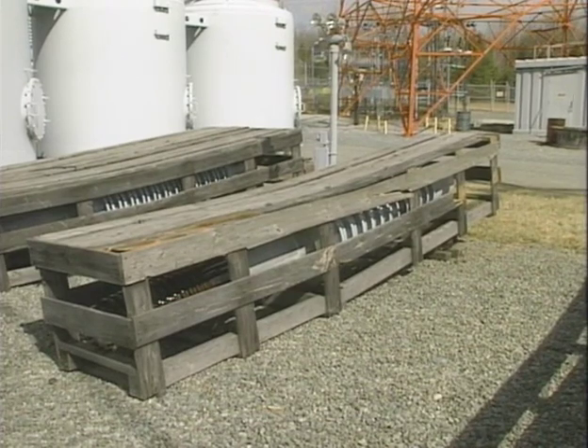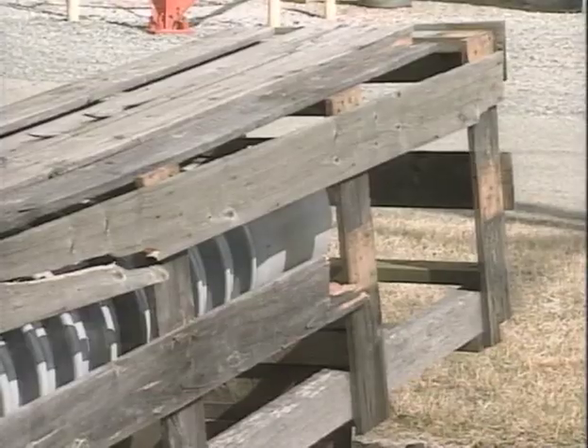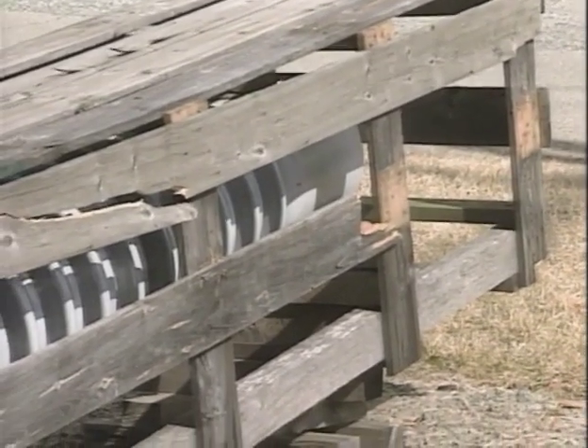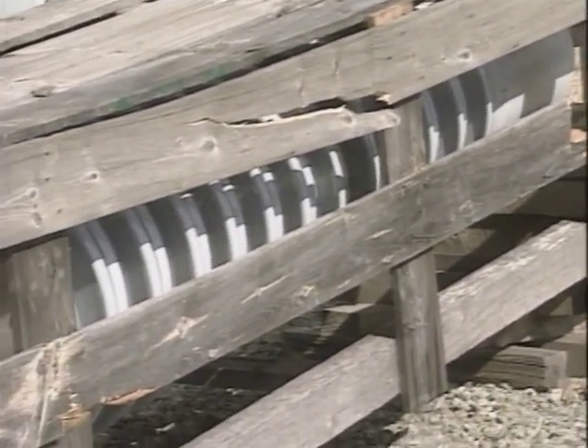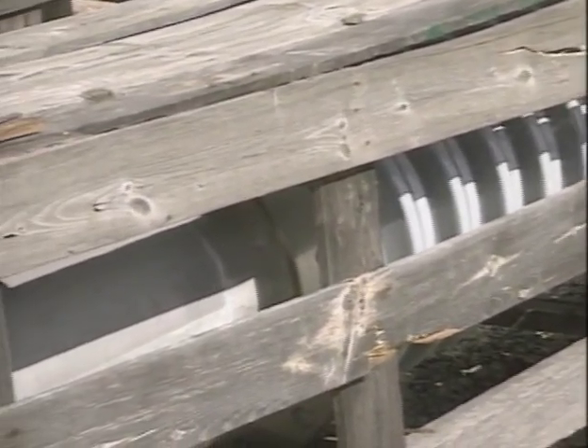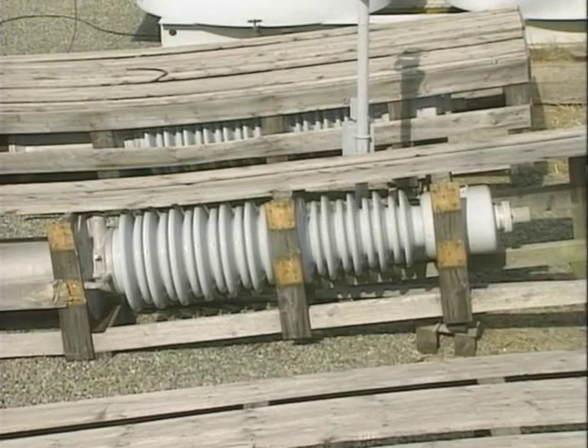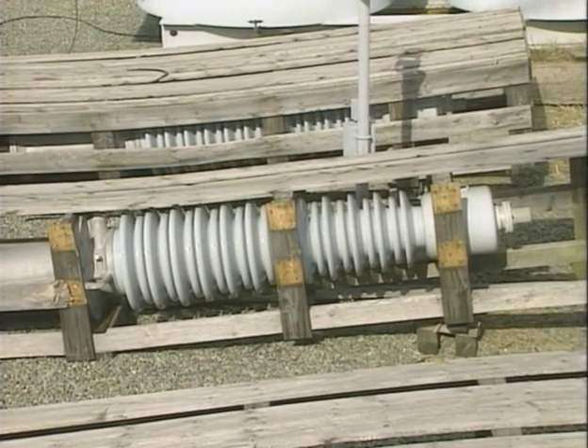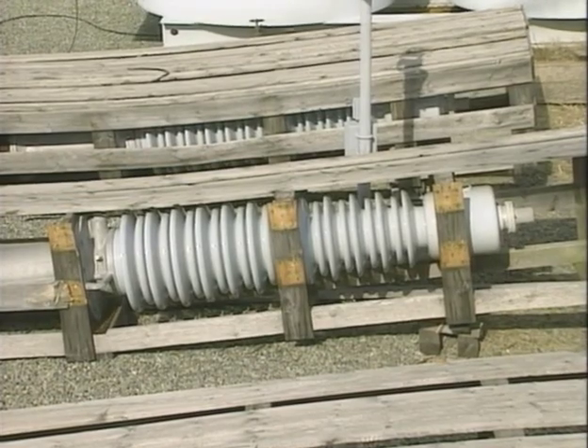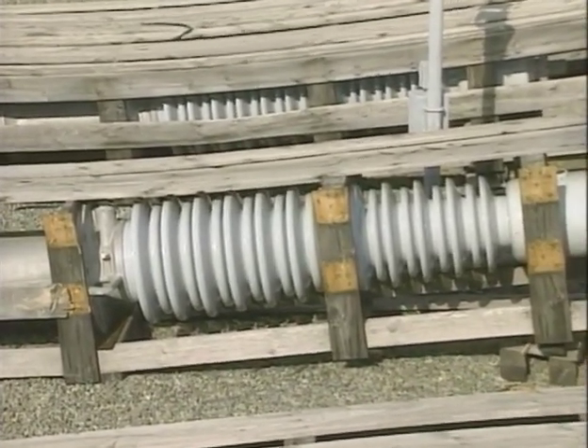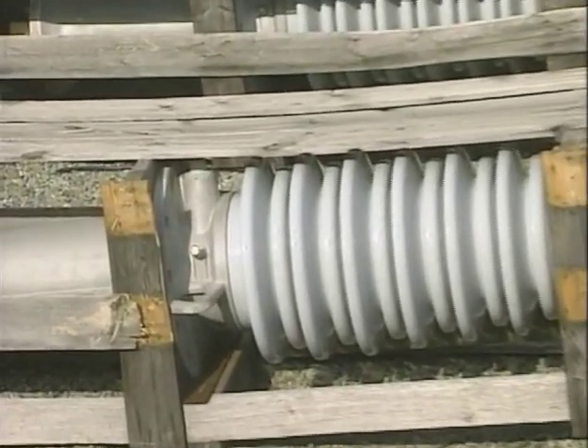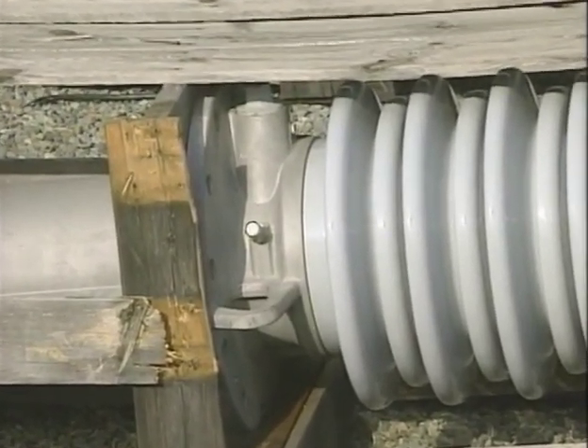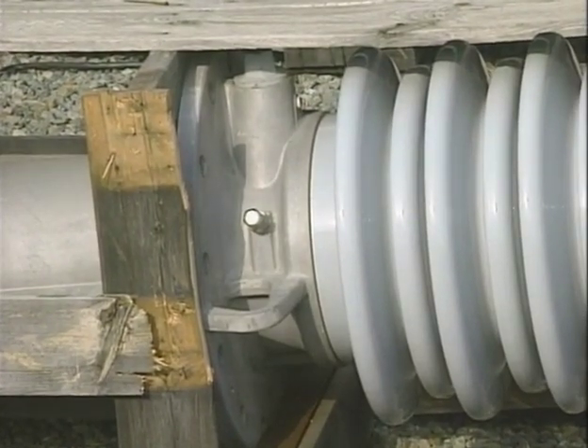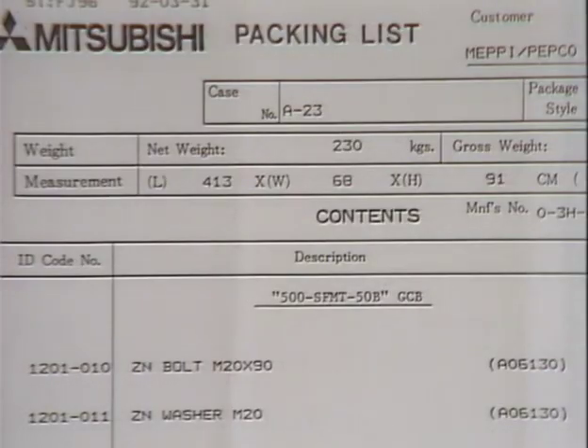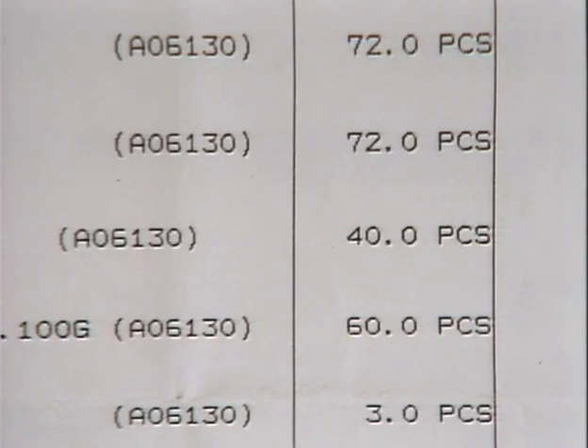If a breaker is delivered with some of its parts packed separately in crates, the crates should be checked for damage when the breaker is received and before the crates are unloaded. A cracked or broken crate might be a clue to damaged parts inside the crate. If damage is suspected, the crating should be removed enough so that components inside can be inspected. The crating and any other packing material should be removed carefully to avoid causing damage. Porcelain bushings should be handled with special care so that they're not cracked or chipped. In addition to being checked for damage, all parts should be checked against the packing slip to make sure that no parts were inadvertently left out of the shipment.